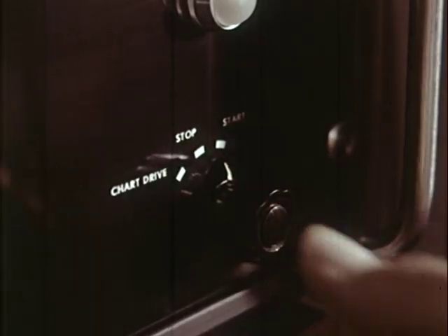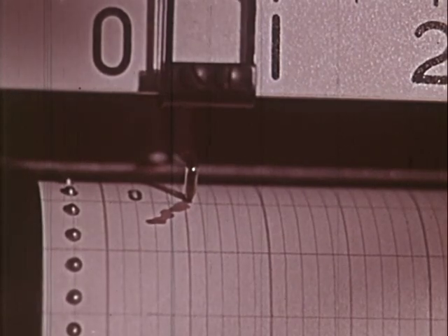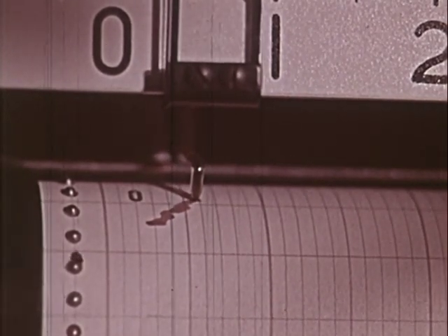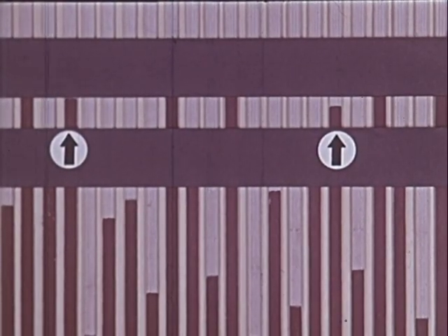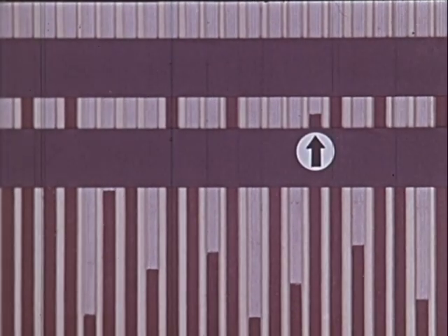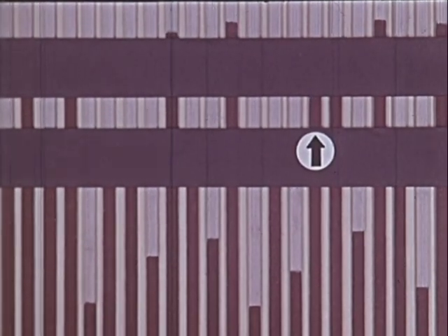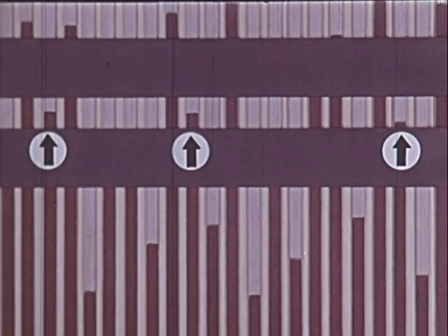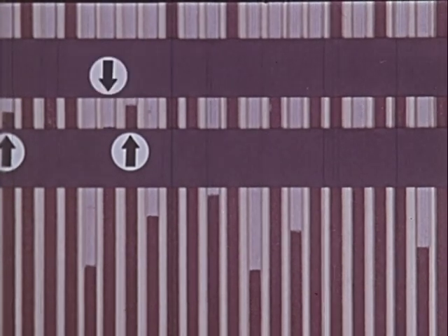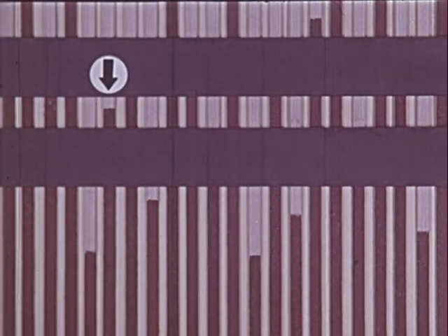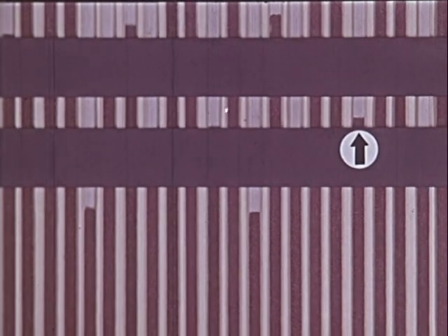Let's see how the spectrum is now depicted. When representing gain scanning, it is shown that an increase of the supply voltage of the detector results in a higher amplification of the pulses. The mutual relation of the pulse heights is maintained. By continuously increasing the amplification, pulses are successively brought into the channel. With this method of operation, the relative channel width does not change during the procedure. Complex spectra are presented in a more favorable way.